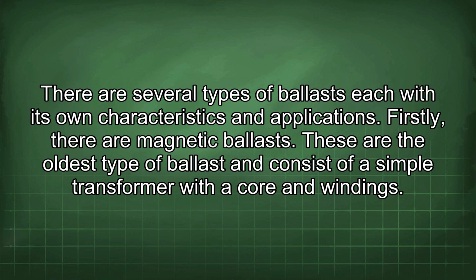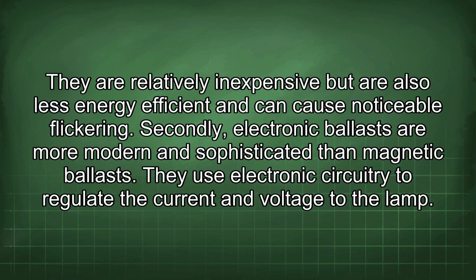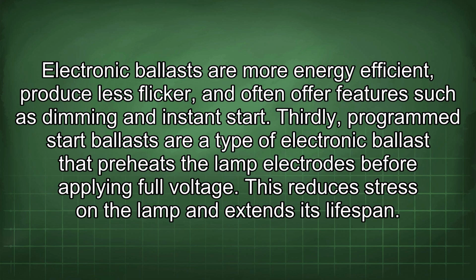These are the oldest type of ballast and consist of a simple transformer with a core and windings. They are relatively inexpensive but are also less energy efficient and can cause noticeable flickering. Secondly, electronic ballasts are more modern and sophisticated than magnetic ballasts. They use electronic circuitry to regulate the current and voltage to the lamp. Electronic ballasts are more energy efficient, produce less flicker, and often offer features such as dimming and instant start.